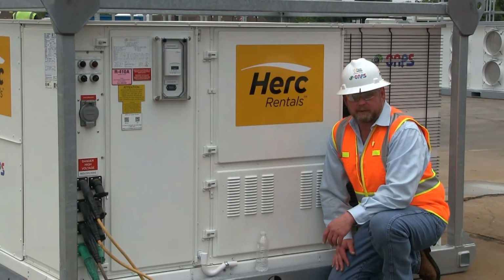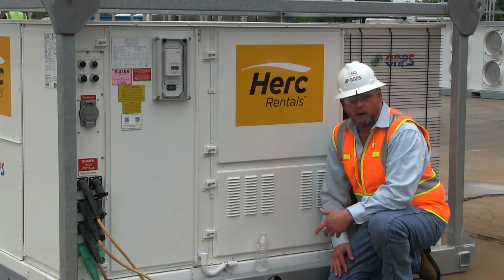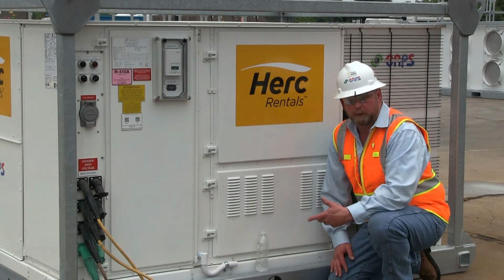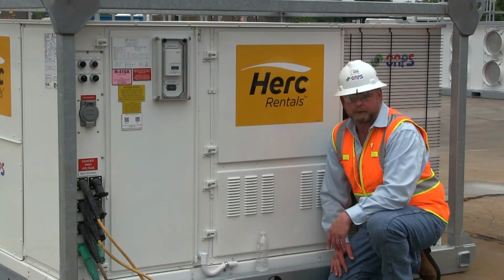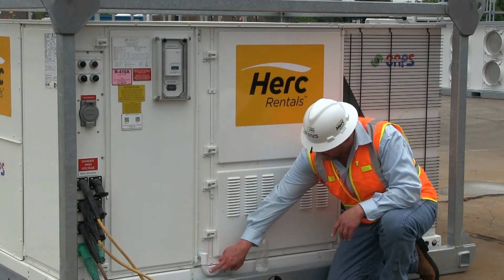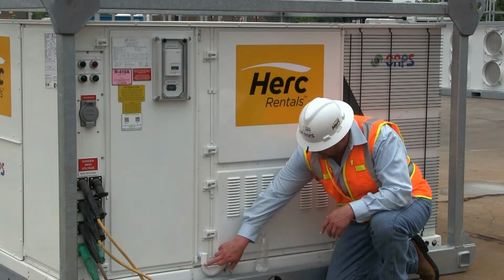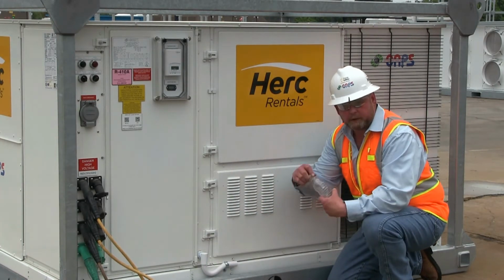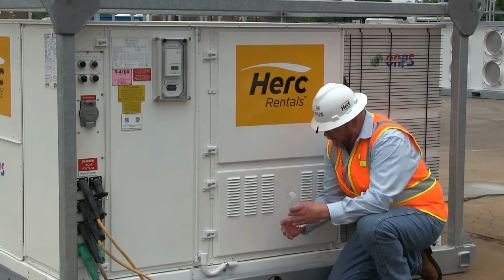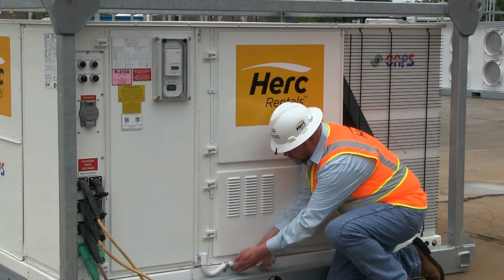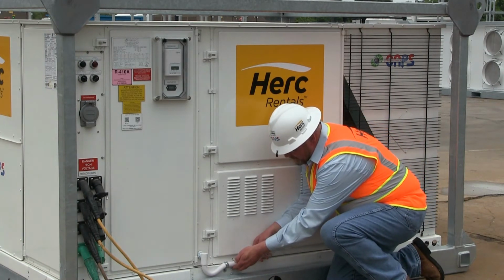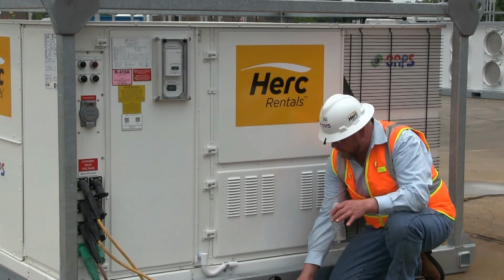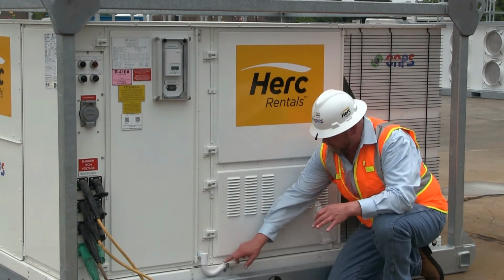Our next step is to prime our condensate traps. All HVAC units that have a cooling coil in them are going to produce condensate. You'll note here that we have a P-trap here that needs to be primed. Usually you use a bottle of water or a hose. You're simply just going to run some water down into the P-trap so that it gets a good prime on it. That way when you do start the unit up under operation, the trap is primed and the unit will drain properly.